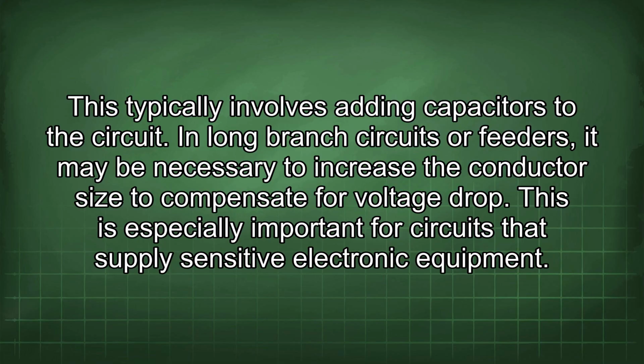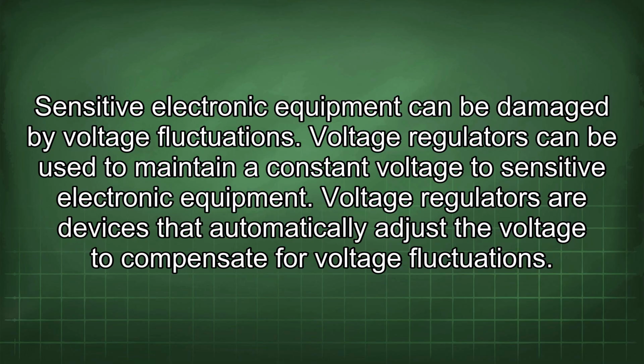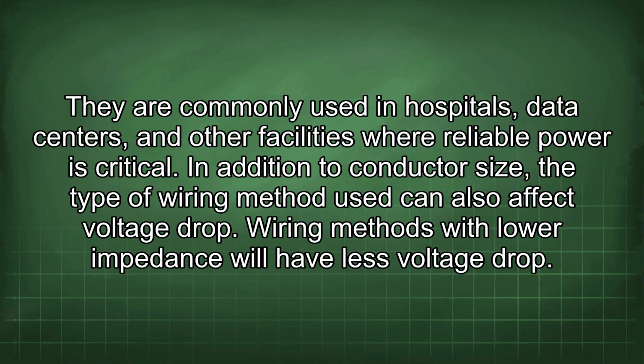In long branch circuits or feeders, it may be necessary to increase the conductor size to compensate for voltage drop. This is especially important for circuits that supply sensitive electronic equipment. Sensitive electronic equipment can be damaged by voltage fluctuations. Voltage regulators can be used to maintain a constant voltage to sensitive electronic equipment. Voltage regulators are devices that automatically adjust the voltage to compensate for voltage fluctuations. They are commonly used in hospitals, data centers, and other facilities where reliable power is critical.